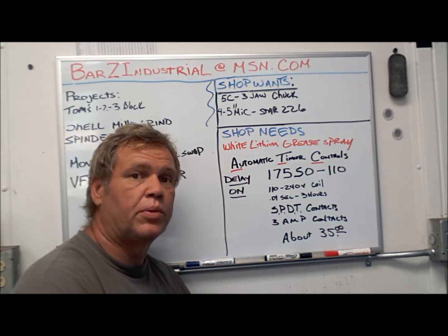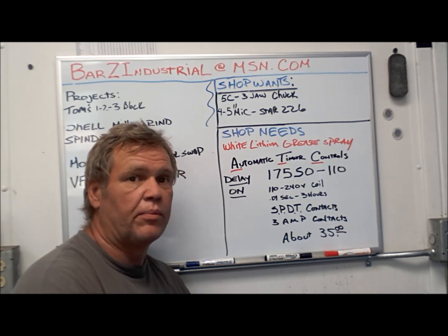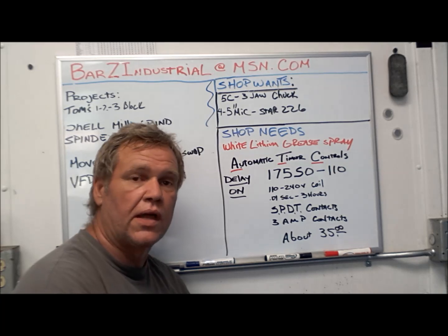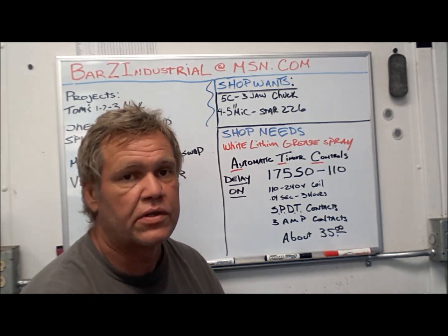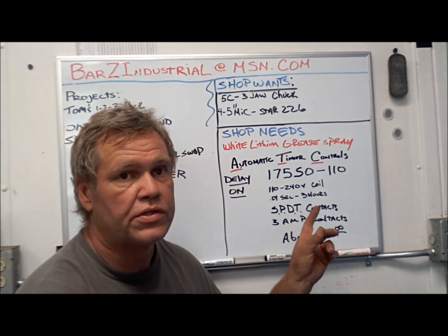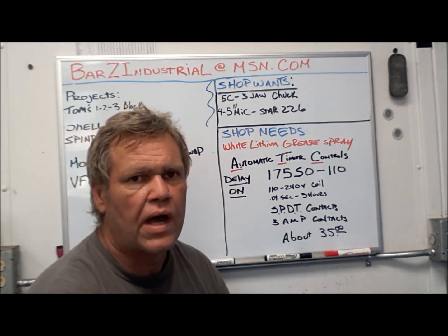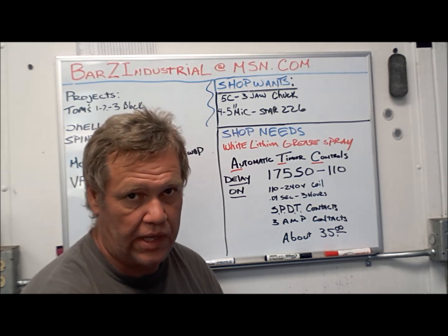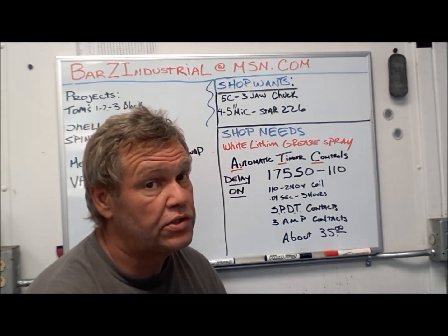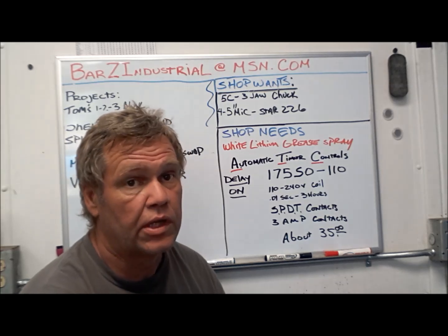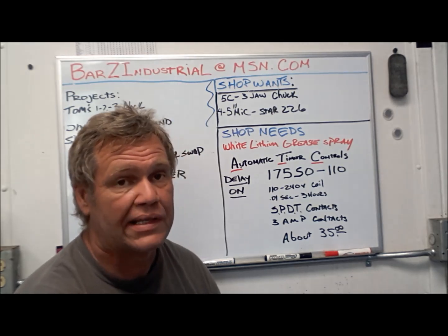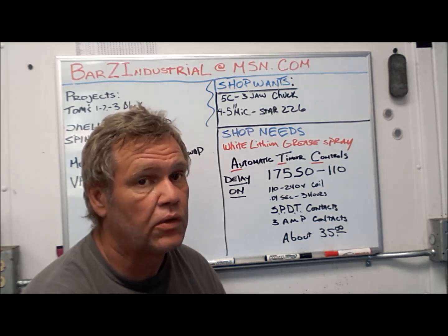But the store bought ones that plug onto tanks for the auto drains, I think they're about 80 or $90. So you're right in the ballpark by the time you buy a solenoid and get it piped in and all that, and then get this timer. So you're right in the ballpark dollar wise. And these are very small units. If you can look them up online, Galco has them. Look up GALCO. There's a supply house for industrial controls and different types of automation, but this will get you an automatic tank drain. And you want to make sure that your solenoid that's used is a normally closed solenoid. Don't get it normally open and try to work it backwards. That's not going to work. You'd have to energize it all the time to keep it closed. And solenoids won't like that. So make sure you've got a normally closed solenoid on your tank.